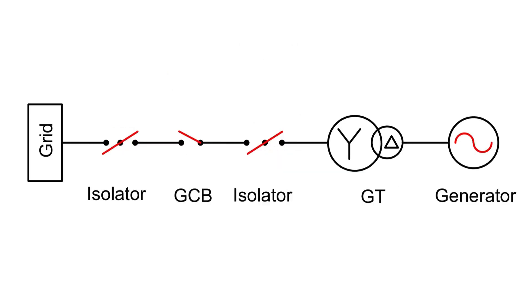Before synchronizing, let's briefly discuss the layout. This is the generator transformer or GT, which steps up the generator's terminal voltage to levels suitable for grid transmission like 220 kV or 400 kV. The generator's output voltage is usually around 15.5 kV or 21 kV.